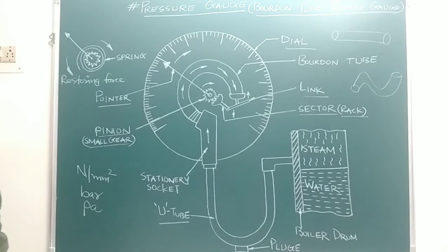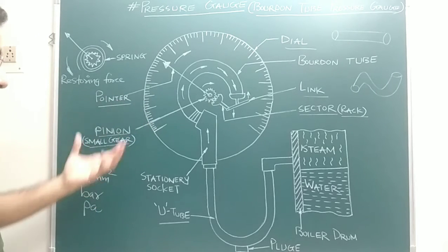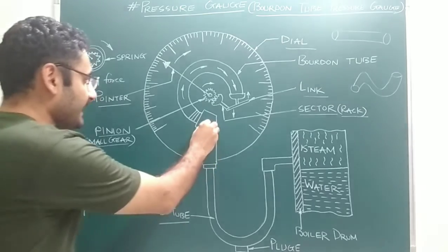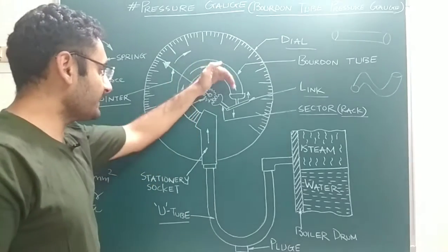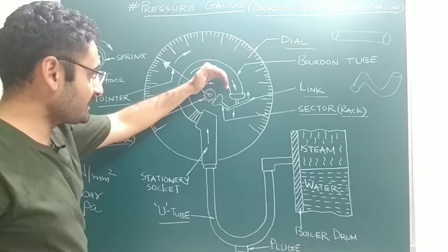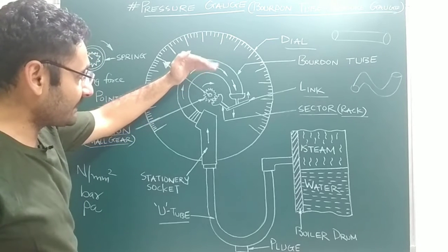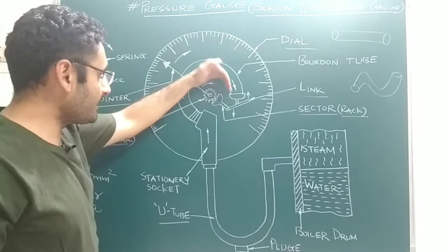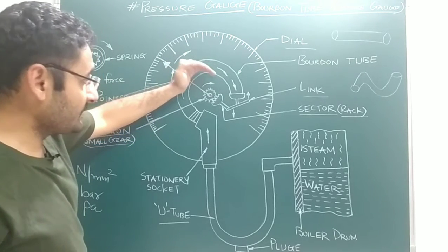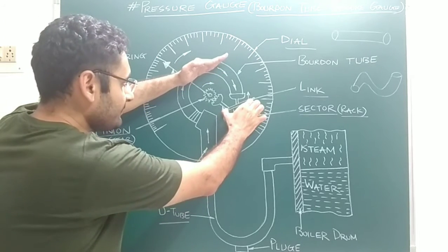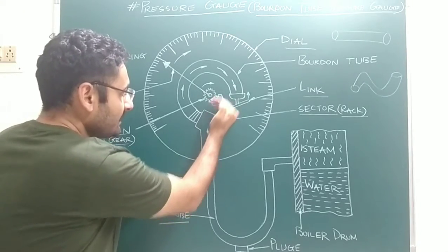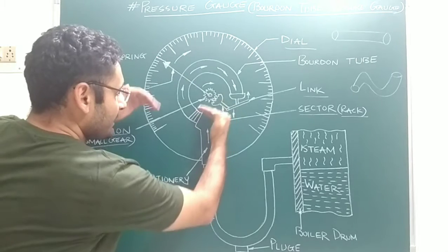Now for the working principle — how we measure the pressure of steam using this device. First, steam enters the U-tube, passes through the stationary socket, and enters the Bourdon tube. When steam enters the Bourdon tube, the pressure inside is high, so the Bourdon tube tries to stretch and become straight. As the Bourdon tube tries to straighten, it pulls the link upward, and the lower portion of the link moves downward, causing the rack to move in the downward direction.